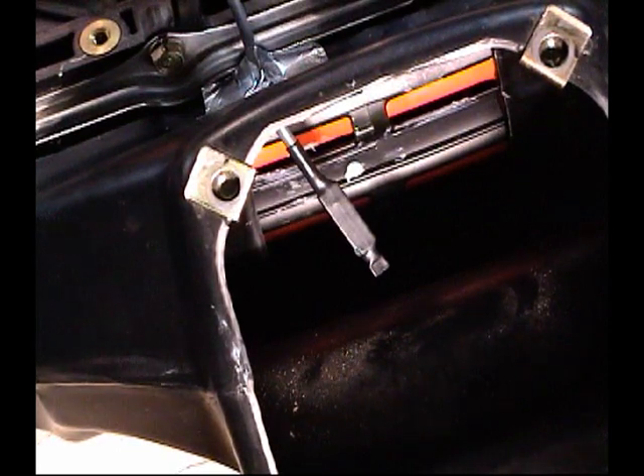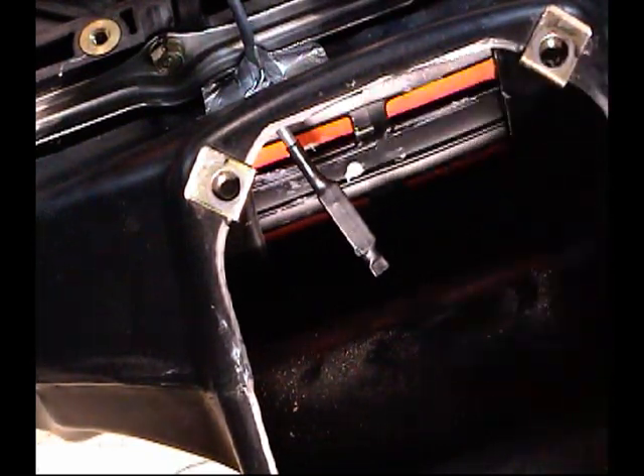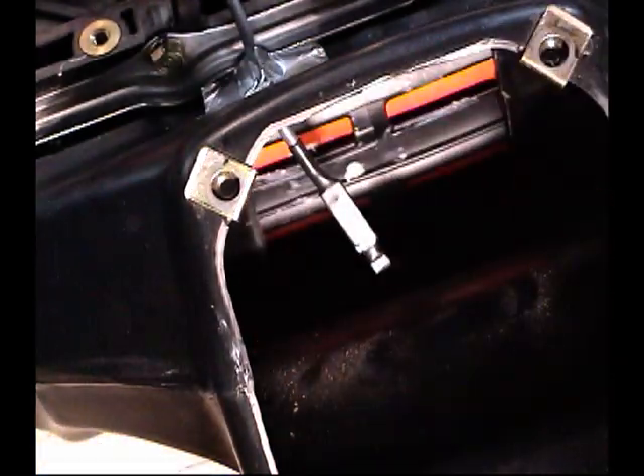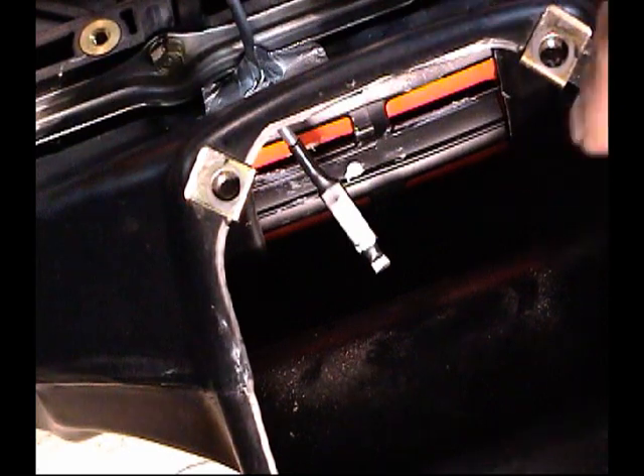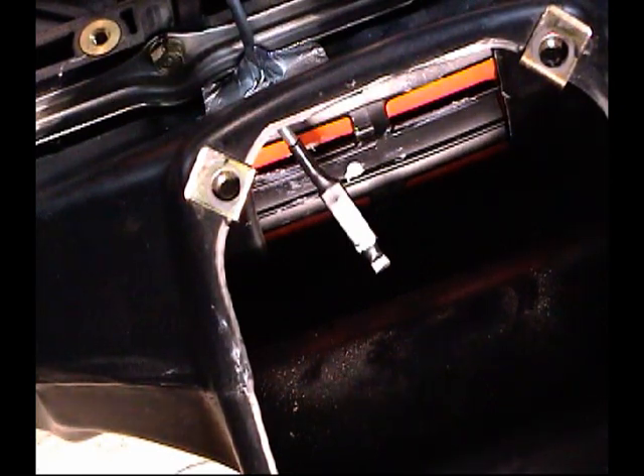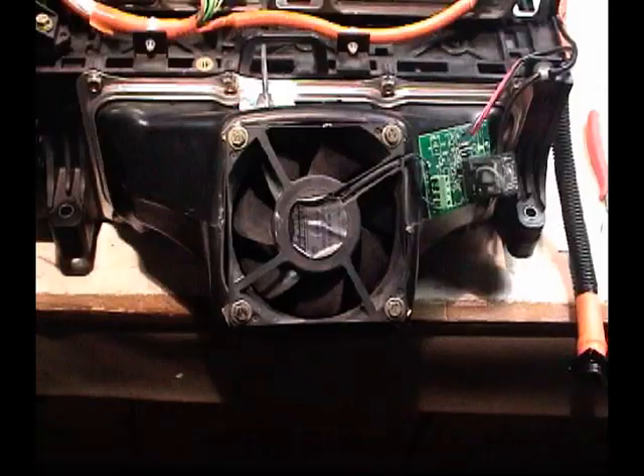What we're looking for in here is, since the air is flowing out of the box, we want the bump on the temperature sensor to be facing inwards, just the way it is now. So now all the air that's being pulled out has to pass by that probe, and it will hit the active side of the probe first, which should take care of our monitoring of temperature.